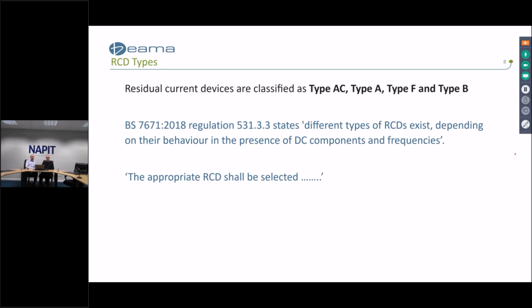Okay, so now to the main substance of the presentation and a major change within the 18th edition of BS 7671. And that's the requirement to select the appropriate type of RCD dependent on the expected load.